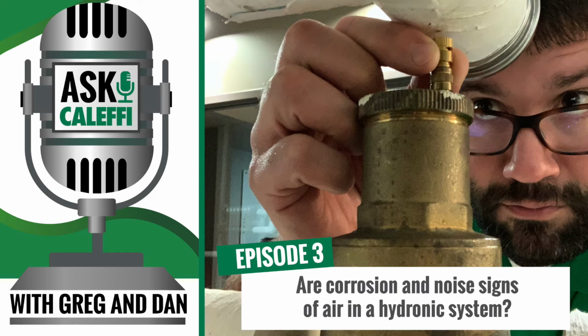So with the added air vent, you've got a larger body with an inlet and an outlet, with a coalescing mesh inside that captures entrained air. The little entrained air bubbles cling to the coalescing mesh. They rise up in the barrel and go through the air vent. Right. Yeah, they're vented to atmosphere.